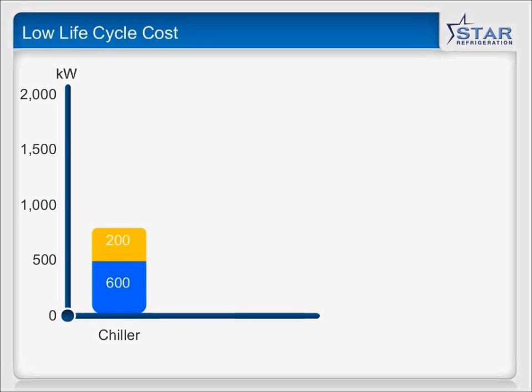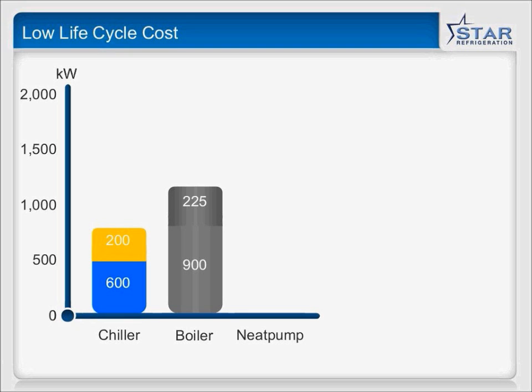Now we call it a neat pump, N standing for natural, and we're doing the same amount of cooling. In theory we should be using more electricity, and we certainly are - it's only by comparison to the old chillers that we're using less. If we ran this plant in cooling-only mode, it would consume less electricity, but we wouldn't get any heating. But the real Brucey bonus, as they say, is that not only do you spend more electricity, but you get all of that back, plus the cooling duty back as heat. So we're getting 900 kilowatts of heat available from our 600 kilowatts of cooling.